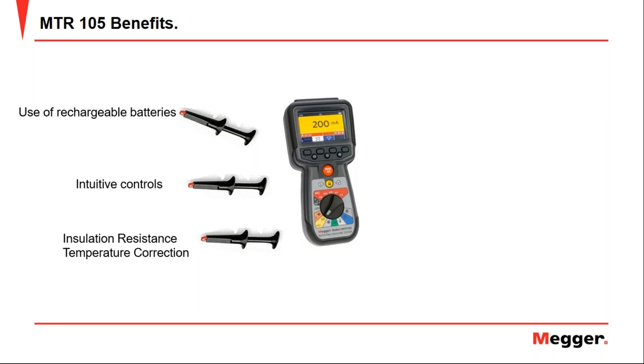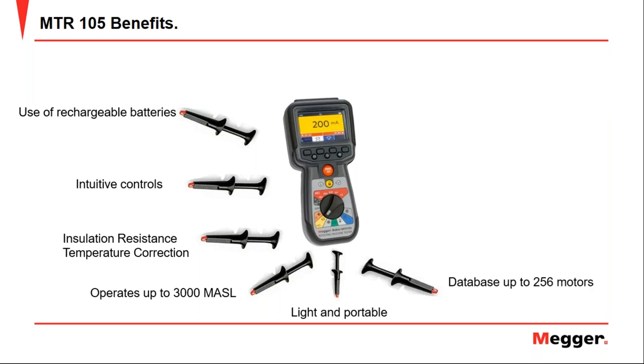Very important point. This equipment can perform the insulation resistance temperature correction, so you don't have to worry about when you do the measurement. You are always going to have the correction of the value in the insulation resistance test. It operates up to 3000 meters above sea level. It is very light and portable. It can handle a database of up to 256 motors, so you can have all this information in the equipment, and you can download it to your PC through the USB flash drive.